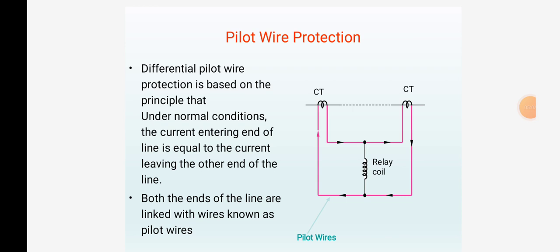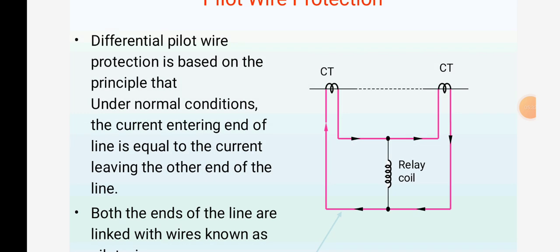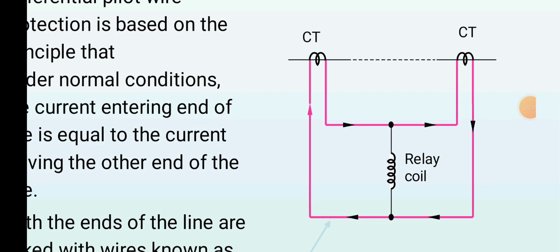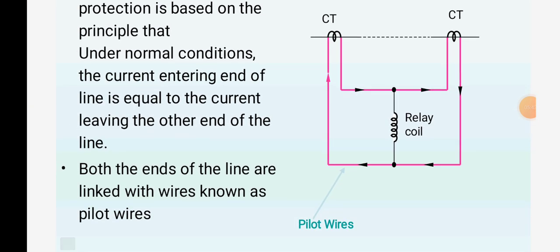Differential pilot wire protection is based on the principle that under normal conditions, the current entering one end of the line is equal to the current leaving the other end of the line. Both ends of the line are linked with wire known as the pilot. The diagram shows two current transformers and the relay coil between them. This line is called the pilot wire.